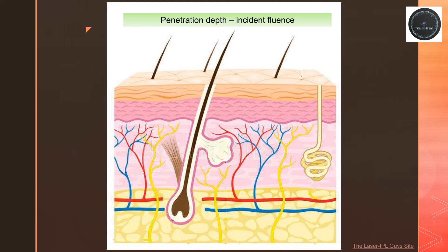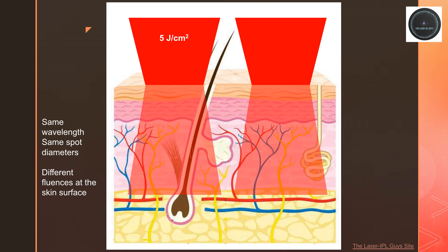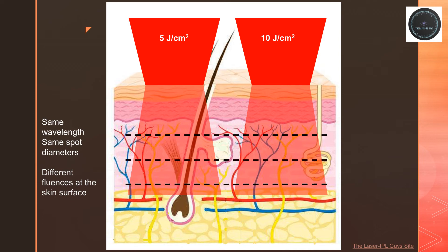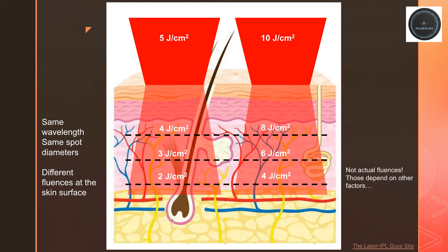Now let's look at the fluence at the skin surface. Let's look at two beams striking the skin surface with the same wavelength and spot diameters, and compare two fluences: one at 5 joules per square centimetre and the other at 10 joules per square centimetre. Fluence decreases exponentially as we go deeper into the skin. The left-hand diagram shows how the fluence may drop from 5 to 4 to 3 to 2 joules per square centimetre. However, if there's a higher fluence at the skin surface, then there will be a correspondingly higher fluence within the skin at different depths. This means that you can generate higher fluences deeper in the skin depending on the fluence at the surface, but you must be careful not to use too high a fluence at the skin surface in case you start to damage the skin.